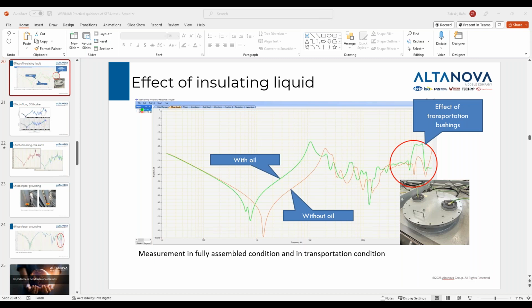All HV or LV phases must have the same trace. Okay, between phases, I already presented, it doesn't have to have the same response depending on the design of the transformer. So it doesn't have to be the same, and when it is not the same, it is good to have reference results for comparison.